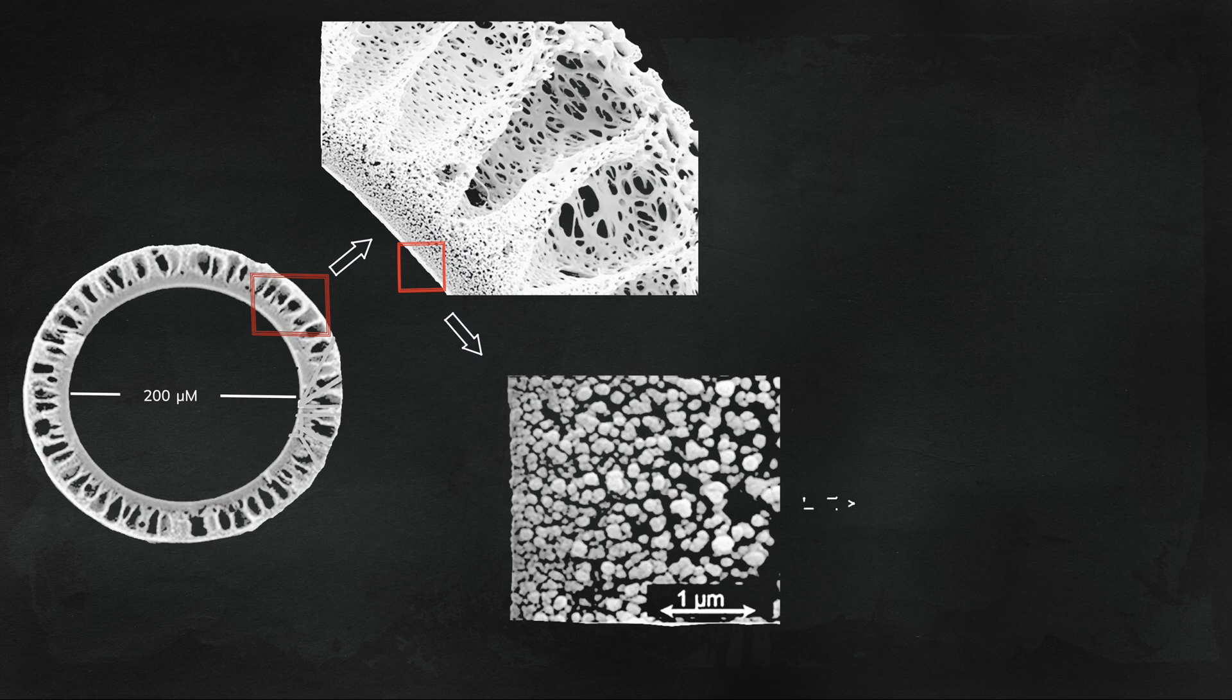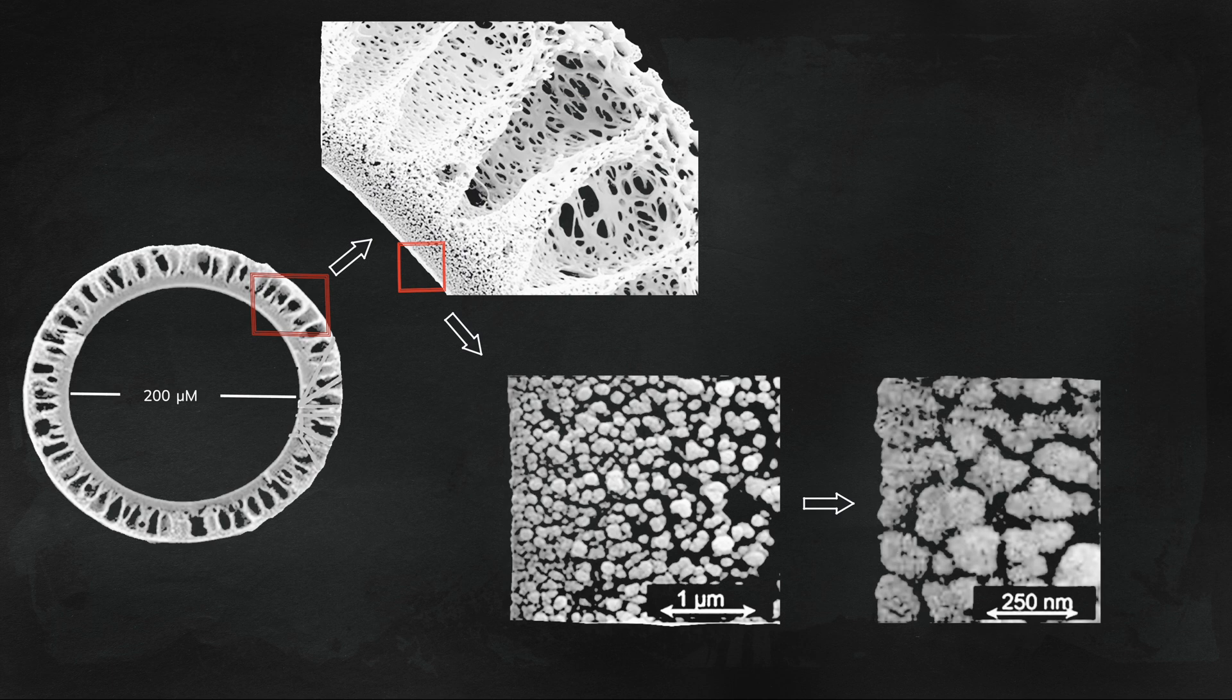An important byproduct of the use of membranes with larger pores is its implications on the quality of dialysis water used. There is significant internal filtration and back filtration that occurs with high flux membranes and more so with medium cutoff ones.